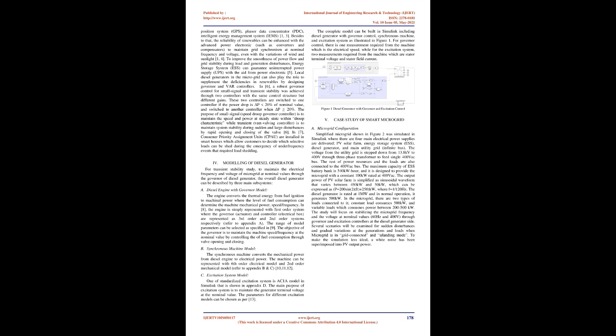The distributed generation, DG, along with local loads can be named as microgrid, MG, while the conventional main power grid is called macrogrid. Microgrid can operate mainly into two modes: grid connected to main grid, which allows the power exchanged between the two grids, and islanding mode, as it is isolated from the main grid. When microgrids are connected to main grid, two-way communications need to be established between the grids to enable power flow monitor and control.